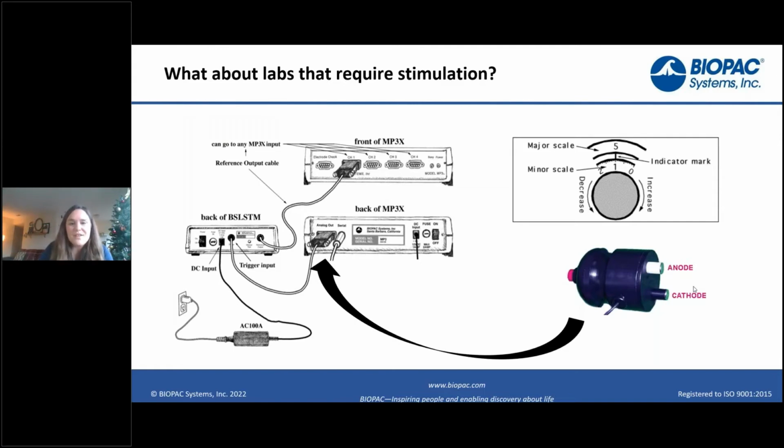There's also another system if you need to adjust the shock more. So if you want to change the level or the intensity, and that all plugs into the analog output. And the analog output is really nice because you can have these additional capabilities like hooking up a stimulator to your system. So remember that when considering these.